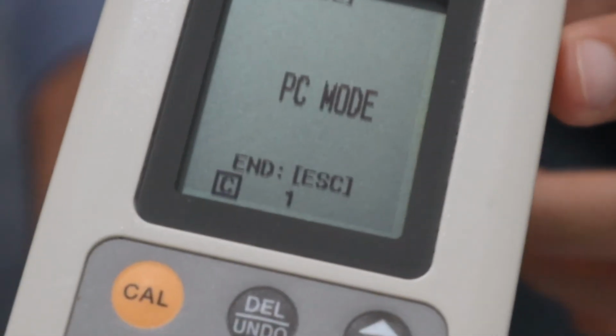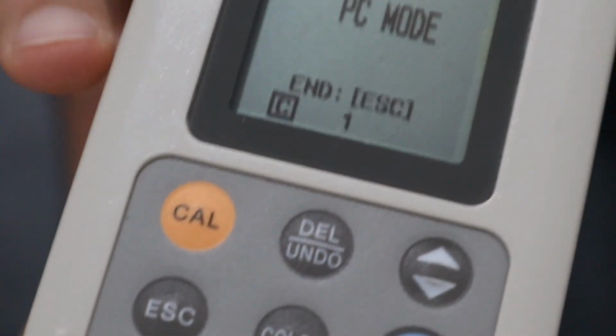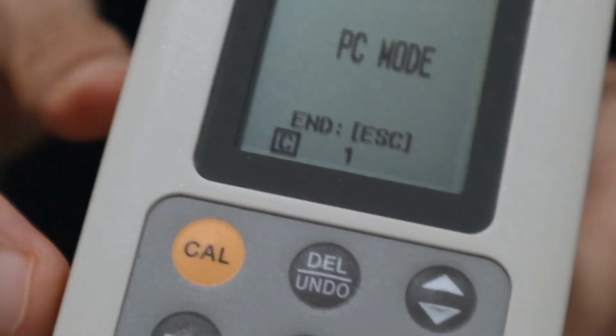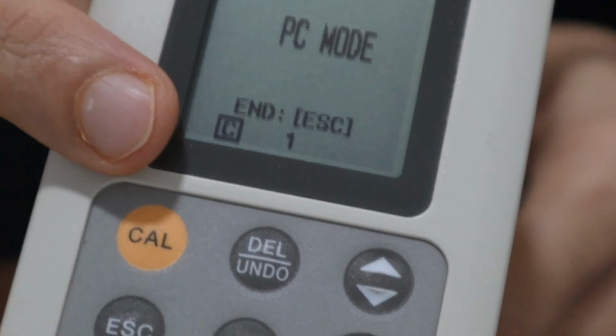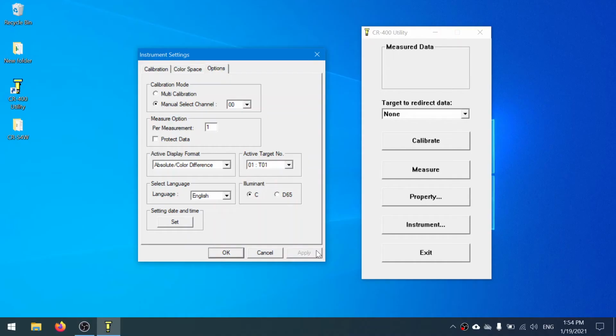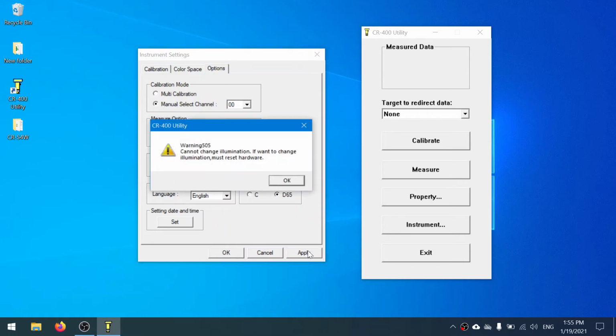Okay. So next thing I want to show you: since this illuminant was set to C, and you want to change it to D65, there's a method to do so. So back on the software, you realize there's an illuminant here, C and D65. It would not be so easy to directly change to D65. So now that I've done measurement in C, if I were to just select D65 here and click apply, it will say warning, cannot change illuminant. If you want to change illumination, you must reset the equipment.